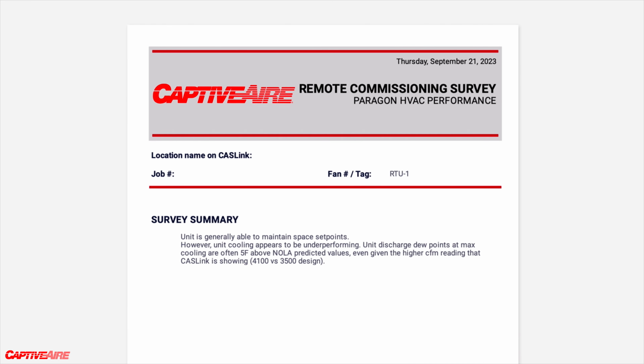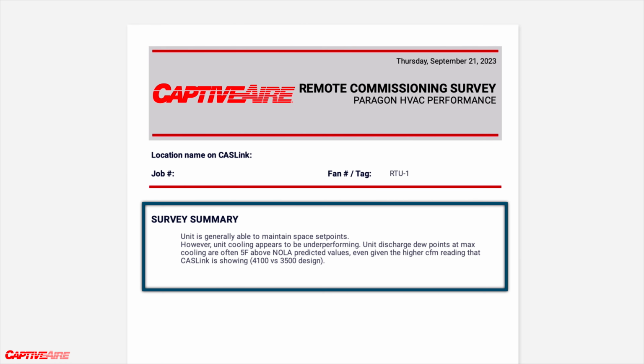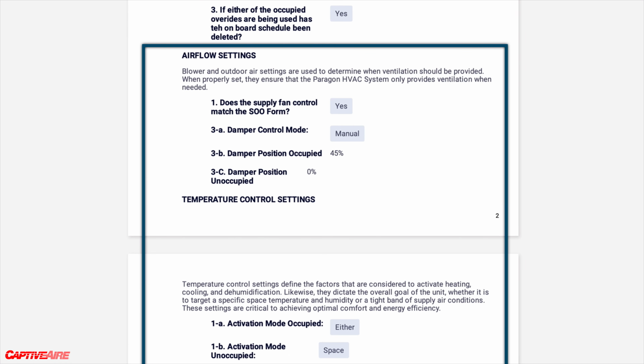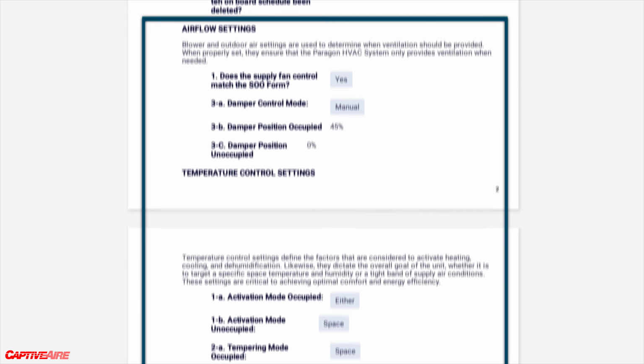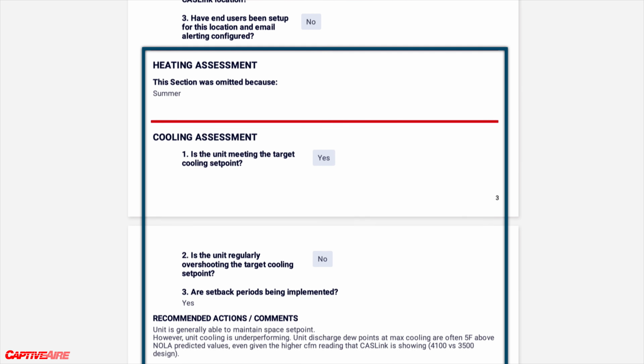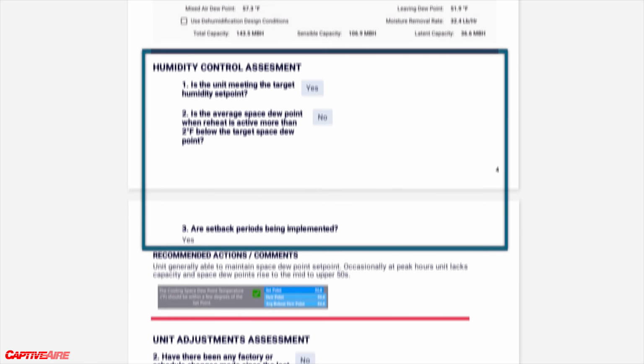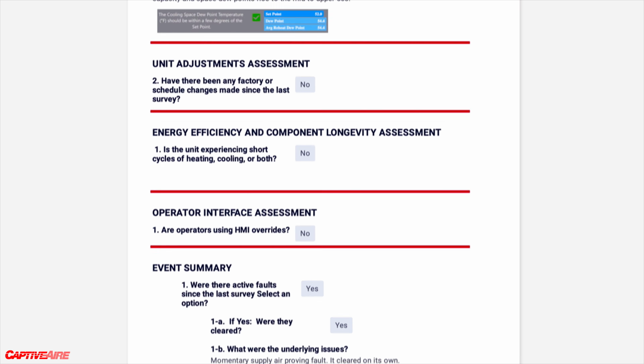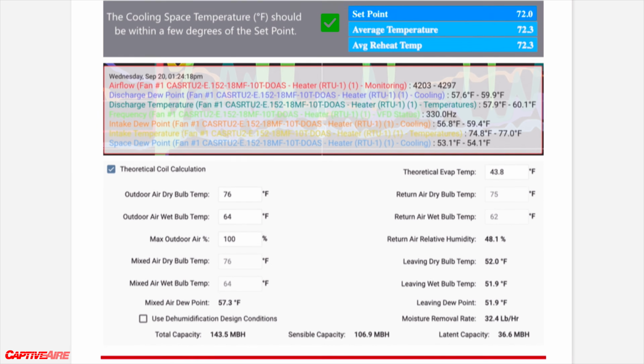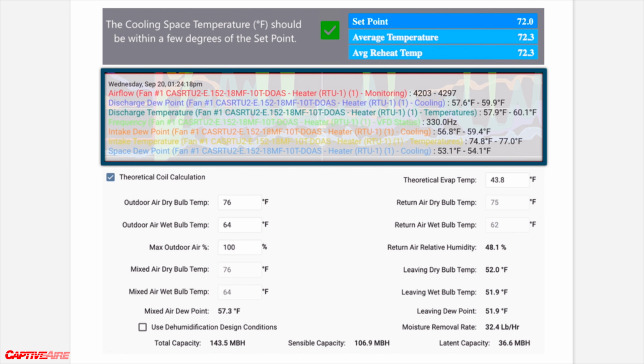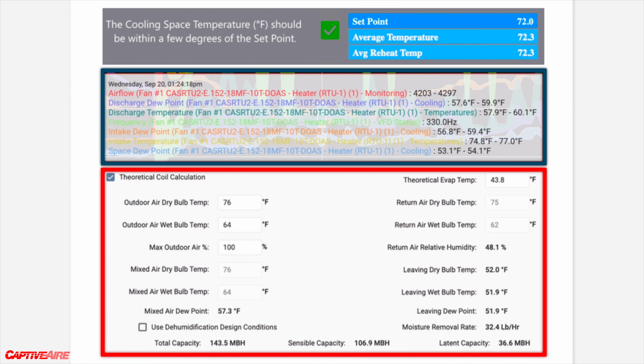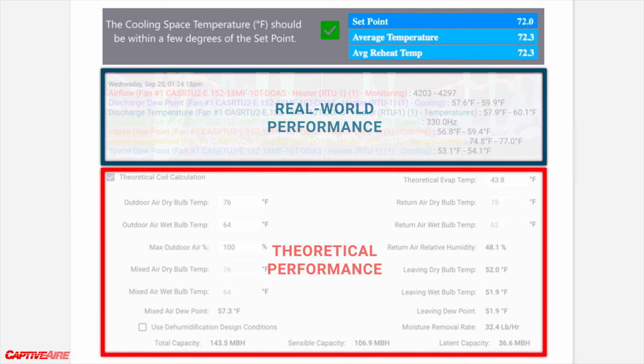Each audit concludes with a custom report, including a summary of the survey findings, set points and settings, and other assessments that ensure heating and cooling are working correctly, that the humidity is well controlled, and that unit cycling is kept to a minimum. They'll tap into screenshots of actual performance in CASLink versus what we would expect operation to fall in versus NOLA. So again, we're making sure this unit is operating at the right outputs versus what we would expect for capacity.